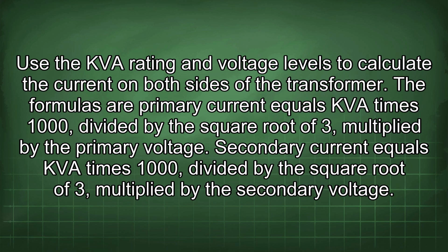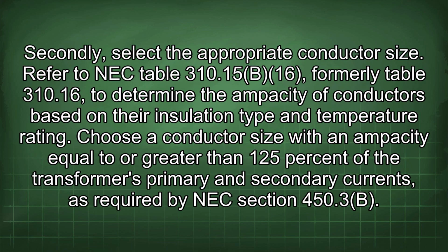The formulas are: primary current equals kVA times 1000 divided by the square root of 3 multiplied by the primary voltage. Secondary current equals kVA times 1000 divided by the square root of 3 multiplied by the secondary voltage. Secondly, select the appropriate conductor size. Refer to NEC Table 310.15(B)(16), formerly Table 310.16, to determine the ampacity of conductors based on their insulation type and temperature rating.